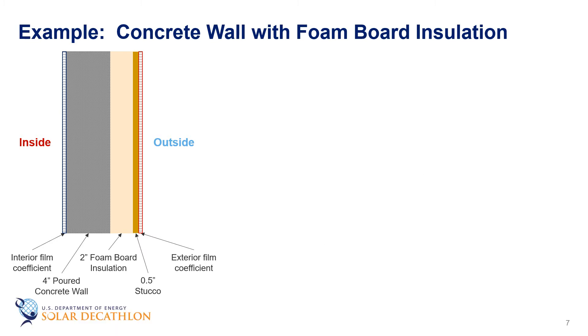So when we really look at the wall from the outside to the inside, we have the exterior film coefficient, the half inch of stucco, the two inches of foam board, the four inches of concrete, and then the interior film coefficient. We need R-values for each of these layers. The R-value for the exterior film coefficient is 0.17 and the interior is 0.68. Remember, this accounts for a small amount of stagnant air on the inside and outside of the wall, and that stagnant air is an insulator.